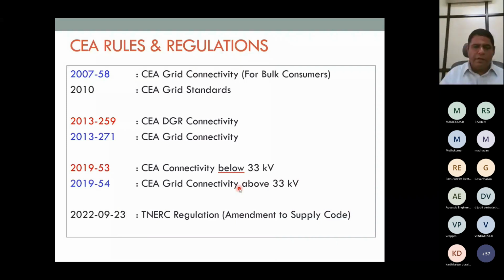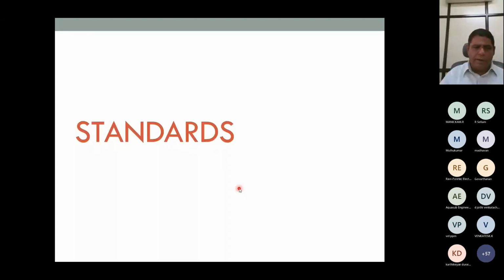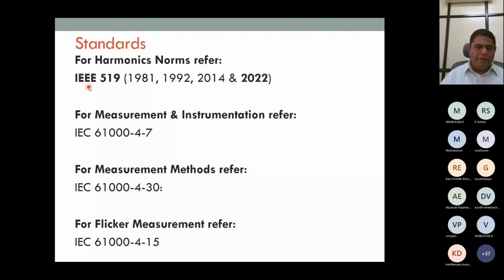So what are all the standards governing, international standards particularly? For harmonics, it is IEEE 519. It was first given in 1981, then in 1992, then in 2014. And right now, what is in force is 2022. For measurement instrumentation, we have to refer to the standard IEC 61000-4-7. For measurement methods, 61000-4-30. And for flicker measurements, this is for informational purpose. We are not obligated for flicker.